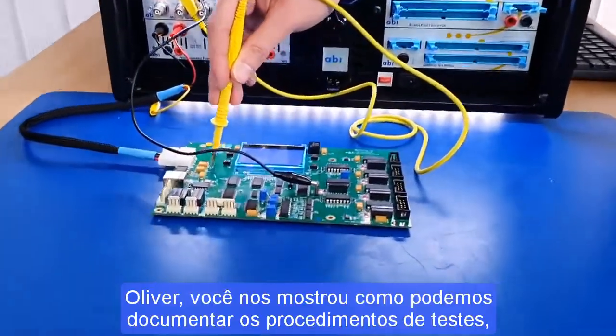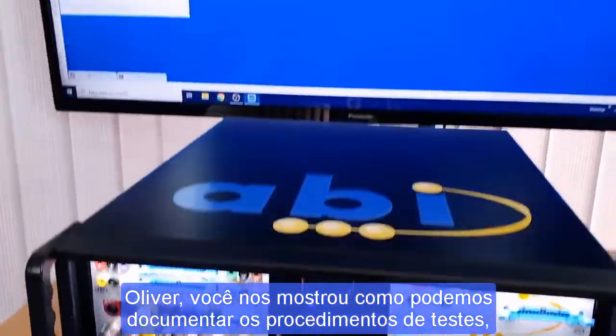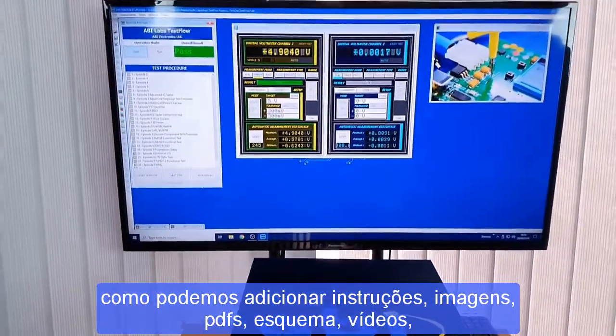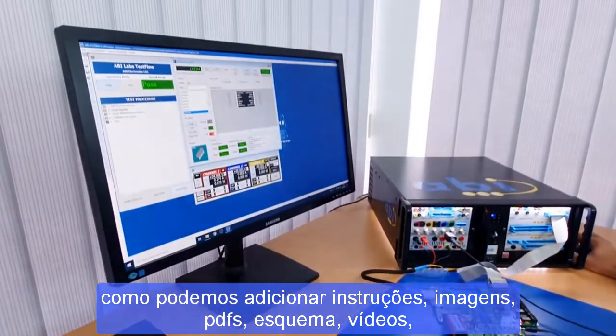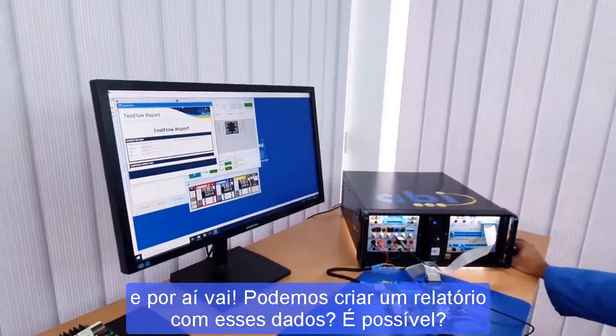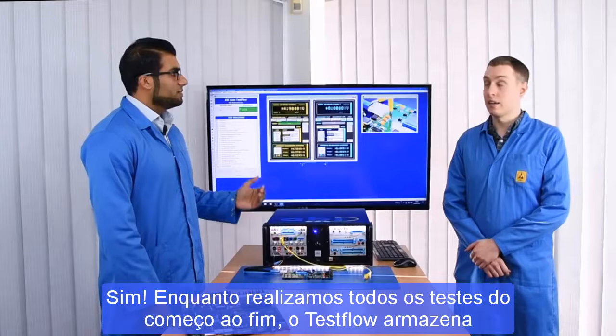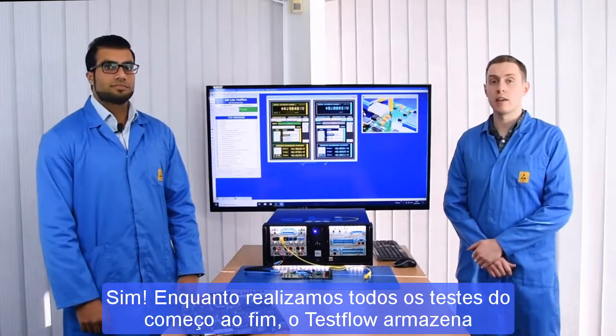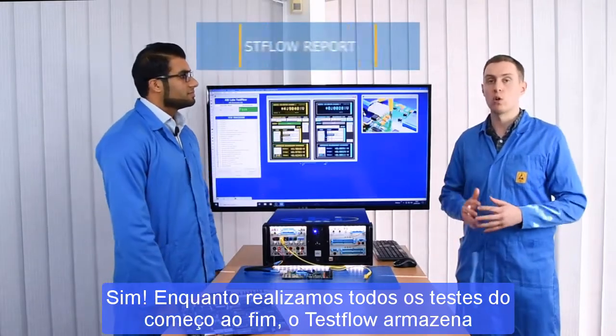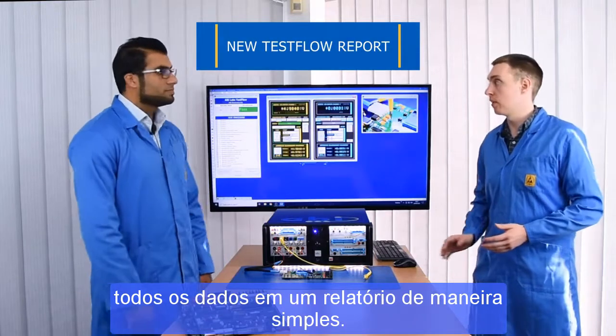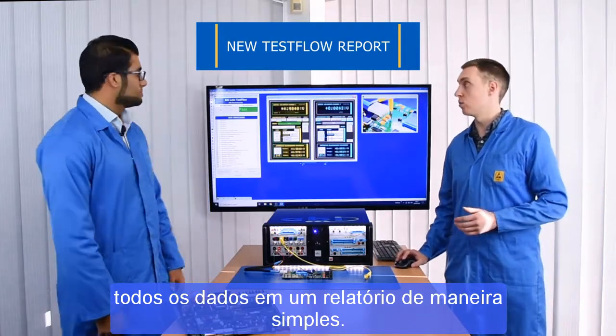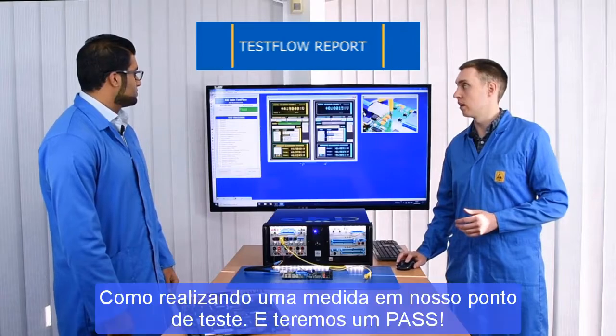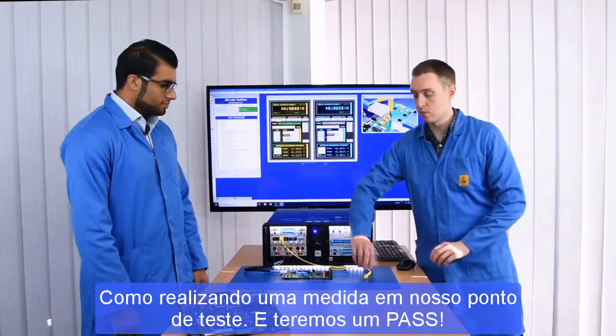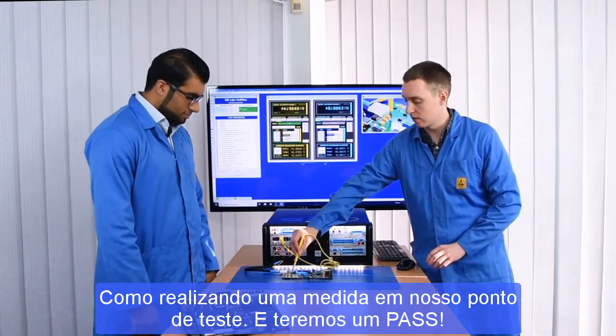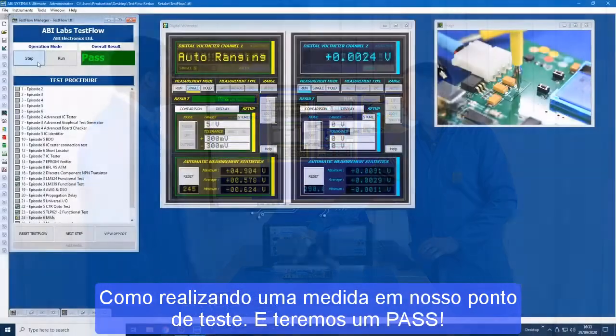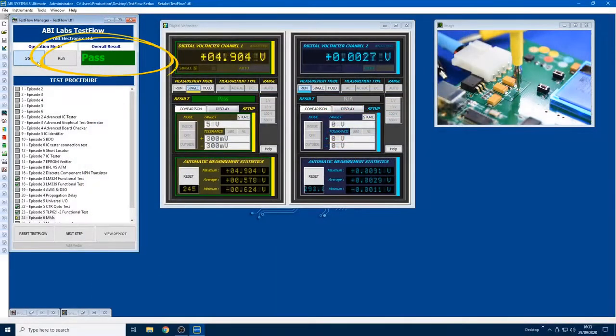So Oliver, you've shown us how we can document our test procedure, how we can add test instructions, images, PDFs, schematics, videos and so on. Can we also save all of this data into a report? Is that possible? Yes, of course. So all while I've been doing all these tests from start to finish, it's been recording all the data in a report. So it's as simple as putting it in step mode, as you would as an engineer, and taking a measurement of our point for our final test, and we'll get a pass.